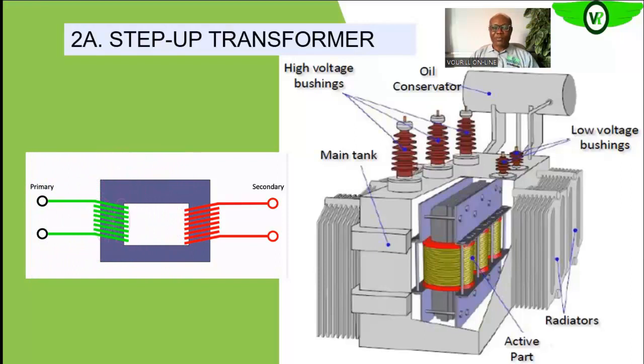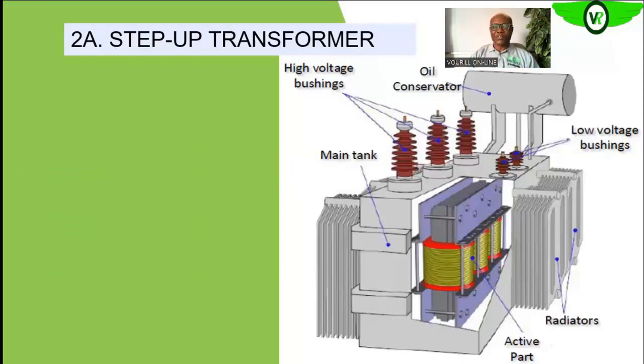In this case, we are looking at the transmission transformer or step-up transformer, which means that its function is to take the voltage from the 11 kV generated to 330 kV to be transmitted. That electrical equipment, the transformer, has some components. The major active part of the transformer is the windings. The windings is where the transformation is actually done. And these windings, as you can see, are wound on an iron core. This is the active part of the transformer.